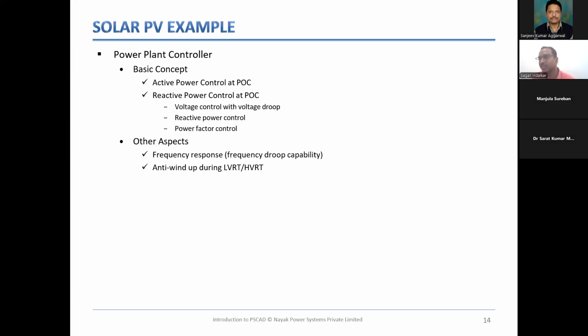Typically, that action is: if the frequency goes above 50.05, it should reduce active power. Why? Because active power is related to frequency. And if the frequency goes below 50 hertz, or 49.90 hertz to be specific, as per the Indian grid code, the plant has to inject additional real power into the grid to support the grid. So that is what your frequency droop control is. These two things become part of your PPC.